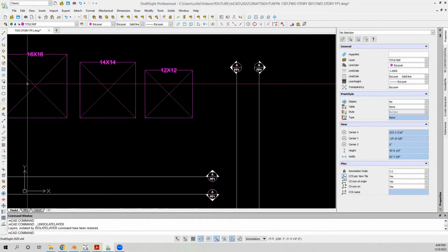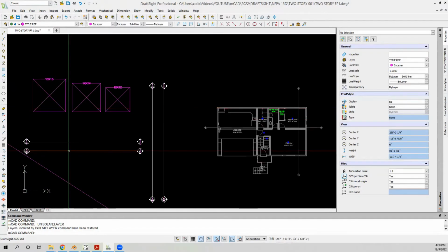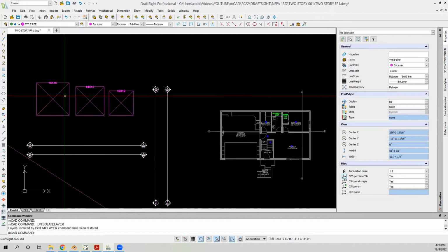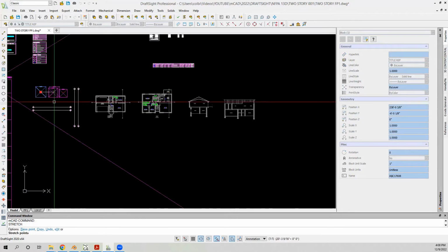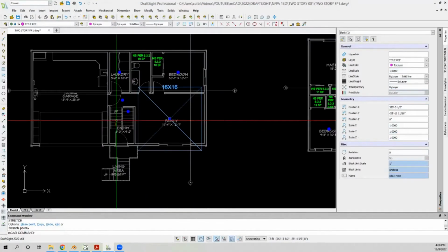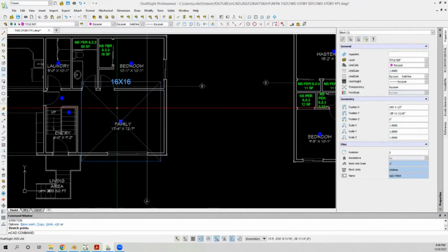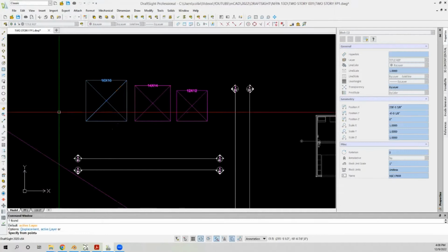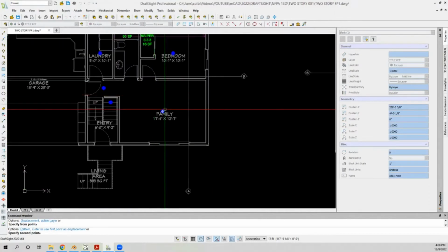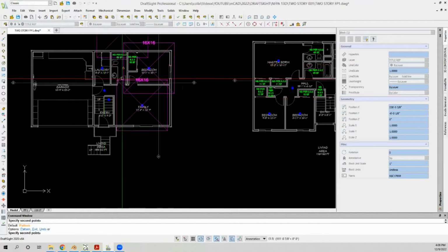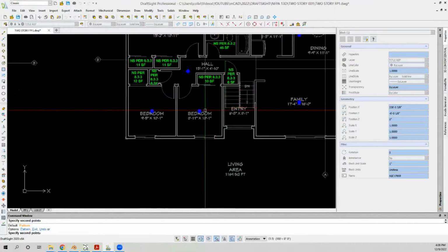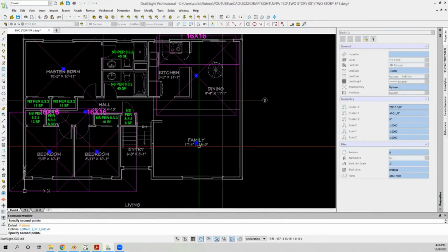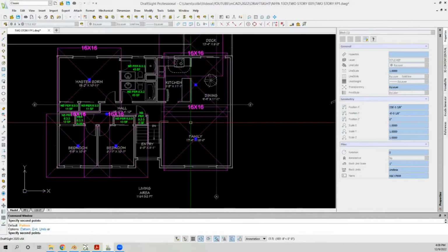We have these tools here that we didn't talk about, but we're using a Senju head. On this one, we're going to be doing 16 by 16 spacing. We can just drop these. That one's pretty obvious. We're going to need 2 heads there. I'm going to copy that instead of move it. We just go and kind of drop them around. Could have put the heads in with this too. That would work pretty good, I guess, and maybe it'd be faster.